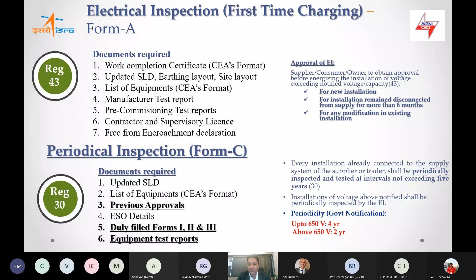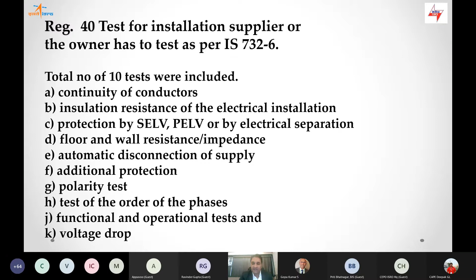Regulation 40, test of the installations by the supplier or the owner, is as per our IS 732-6. A total of 10 tests are included: the continuity test, the IR test, the protective earth resistance, everything. This test has to be complied with by the owner of the organization.